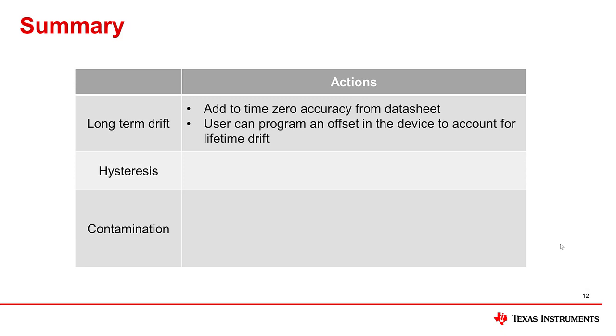Long-term drift is specified in humidity sensor datasheets as the maximum percent relative humidity per year that a sensor will drift in normal operating conditions. If the sensor has an offset correction register, this can be programmed to mitigate drift across the lifetime of the device. Hysteresis should be accounted for in time zero accuracy and is calculated as the delta between the percent relative humidity accuracy during positive and negative humidity sweeps.